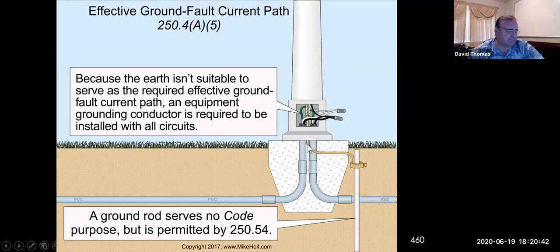like, you go out to Fairfield, and all the poles, parking lot lights have to have this wire going down to the bottom of the concrete base. Before you pour the concrete, you have to wrap this wire at the very bottom, and have the wire come in and land inside what's called a handhole. So the handhole, you land the ground in there, okay? Or you may have to run a ground rod if you didn't do it properly. So you're usually trying to avoid this type of running a ground rod.